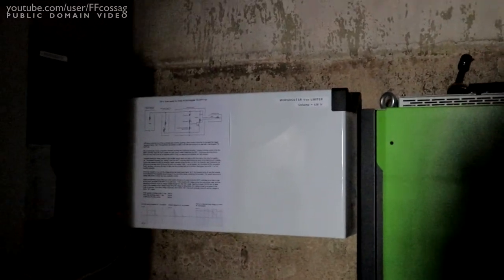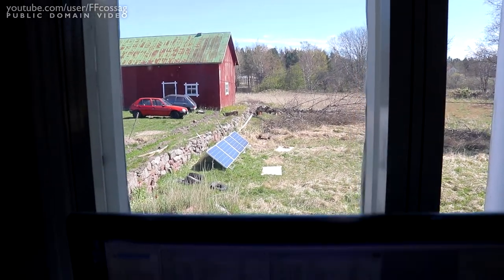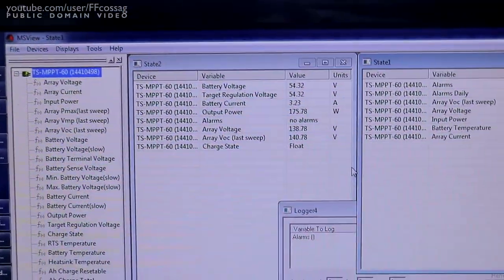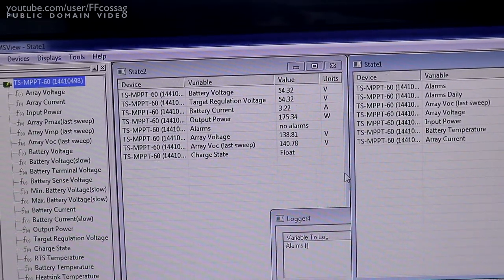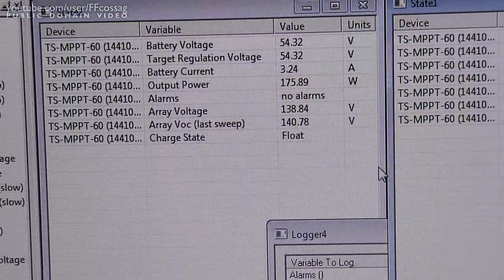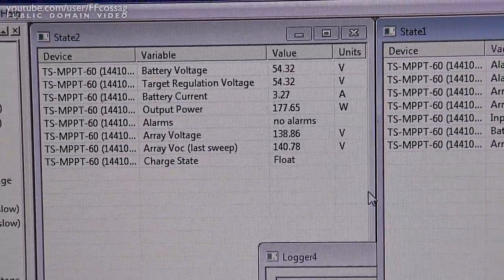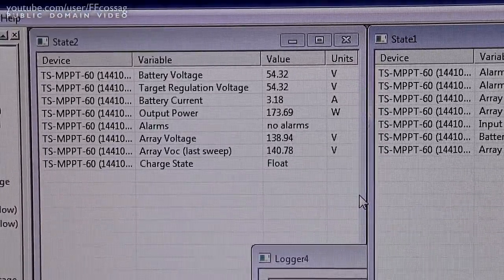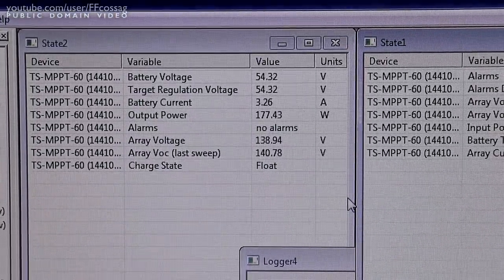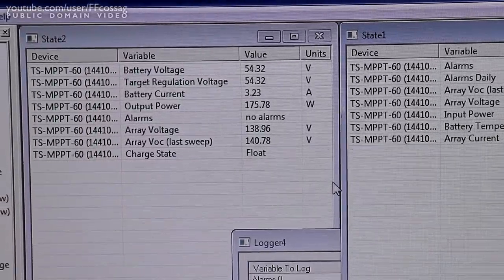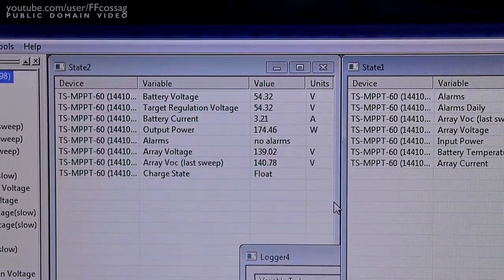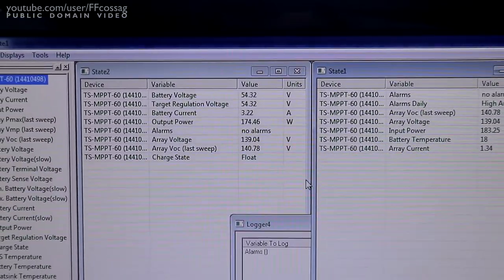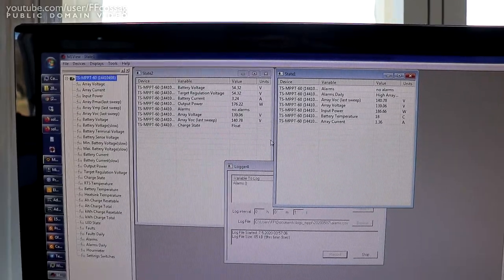It's now a nice bright sunny day. And our solar system has very limited load on it. We're just drawing 176 watts to float charge four batteries. And you can see our array voltage and array VOC are at about 140 volts. 138.9 means the snubber should just about be clipping the voltage. And the VOC of 140.78, that's a bit lower than it used to be. It used to go to about 142. And that means that our new snubber system is working good. And it's clipping that little spike I was getting before when it was starting the sweep. So let's head downstairs and have a look at what's going on.